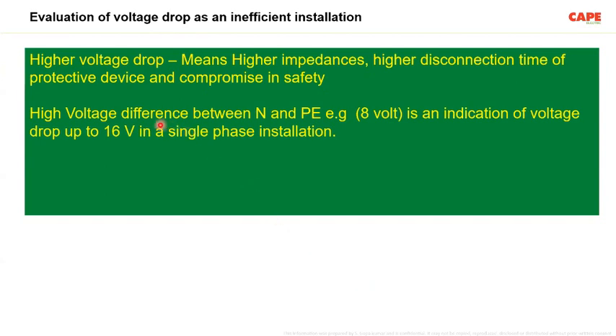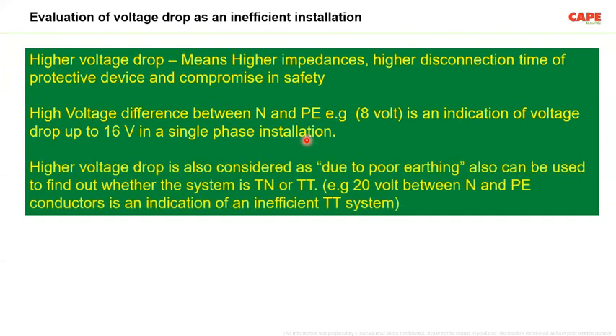a high voltage potential difference between neutral and earth, let us say 8 volt between neutral and earth, is an indication of a voltage drop of up to 16 volt in a single phase installation. So if you measure 8 volt between neutral and earth at one point of an installation, it is an indication that the single phase equipment at that particular place is having a voltage drop of up to 16 volt, which means we are going to the limits. We are not supposed to have that much voltage drop.